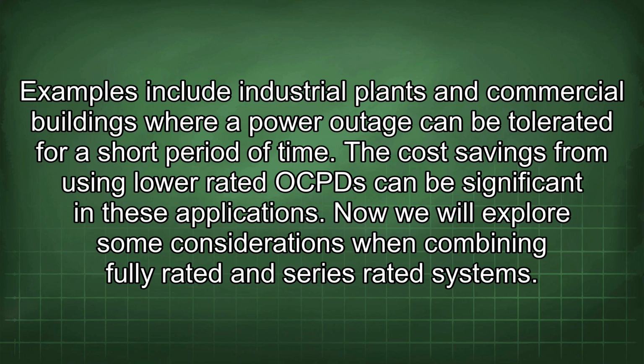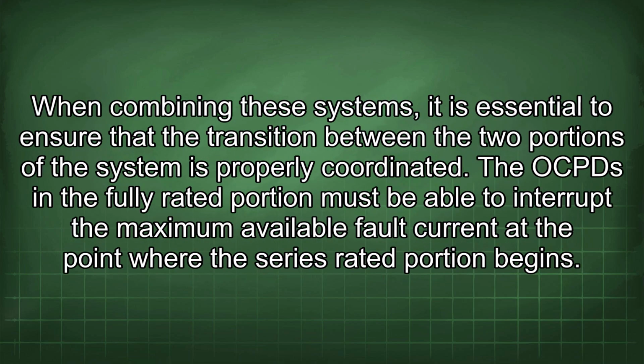The cost savings from using lower-rated OCPDs can be significant in these applications. Now we will explore some considerations when combining fully rated and series-rated systems. When combining these systems, it is essential to ensure that the transition between the two portions of the system is properly coordinated. The OCPDs in the fully rated portion must be able to interrupt the maximum available fault current at the point where the series-rated portion begins.